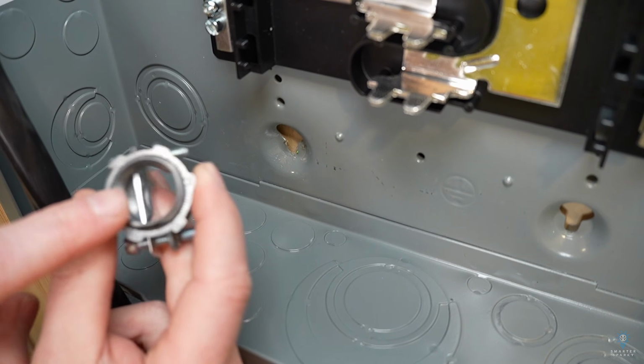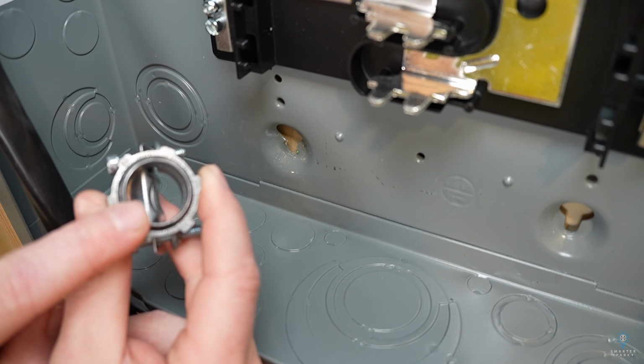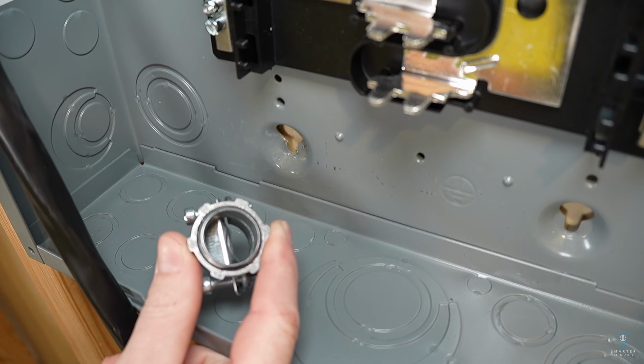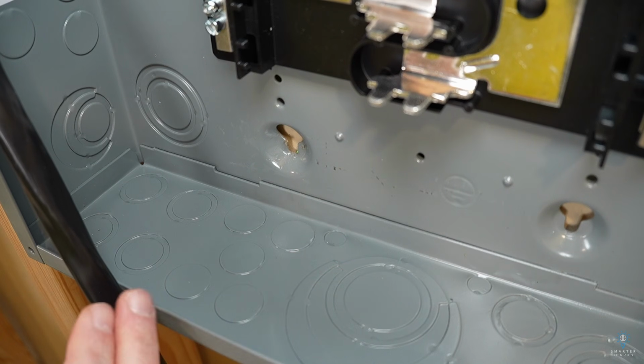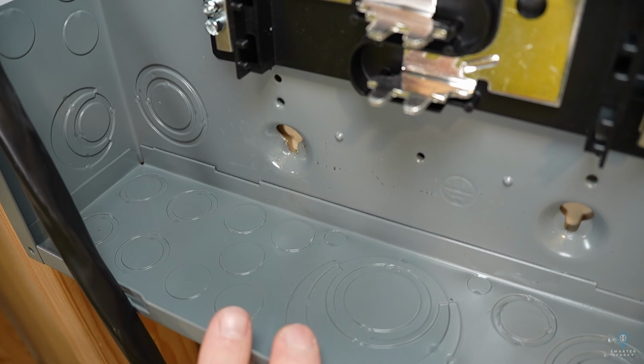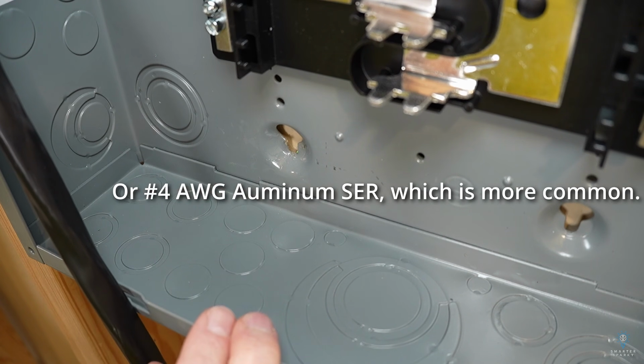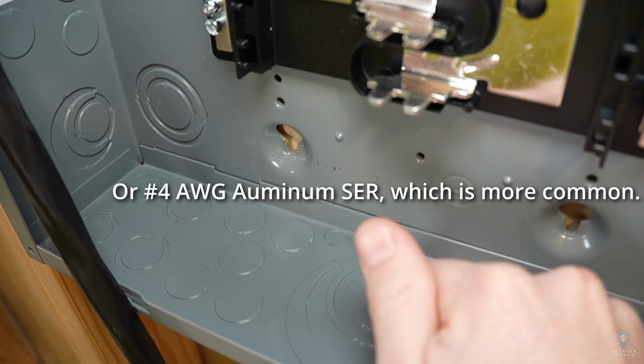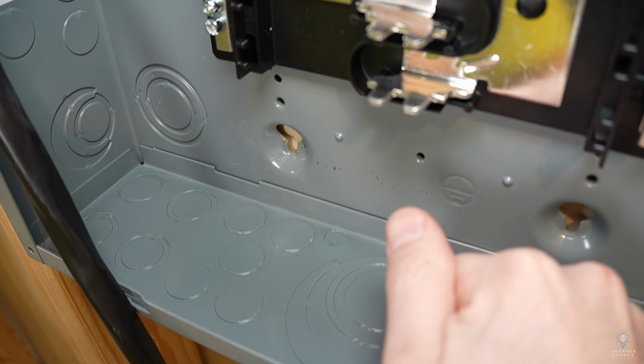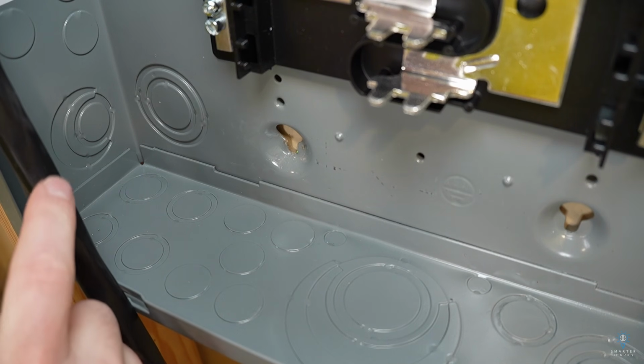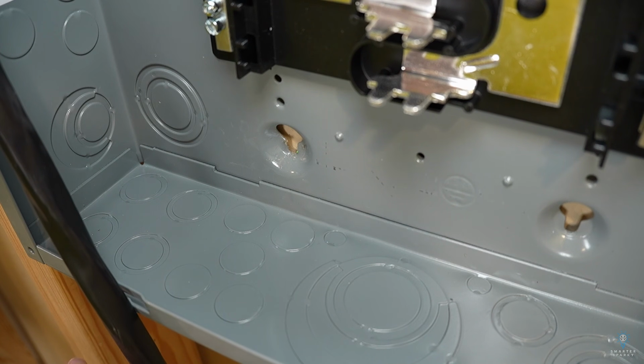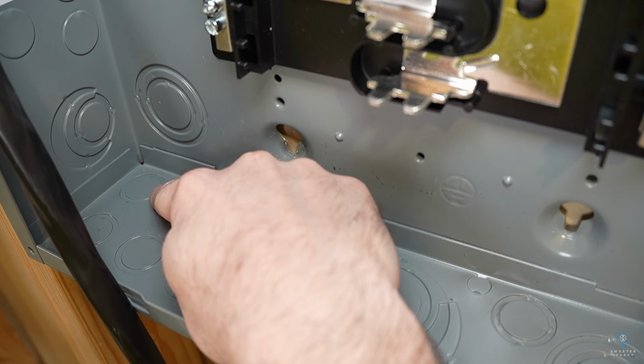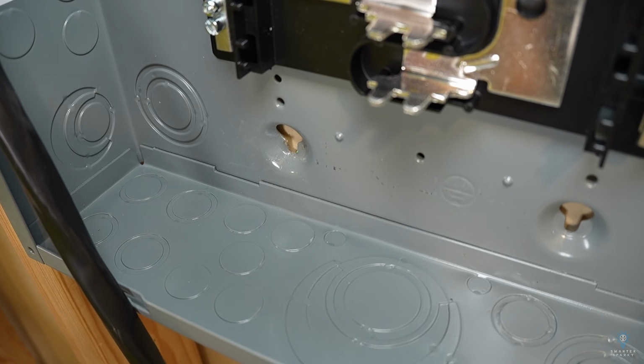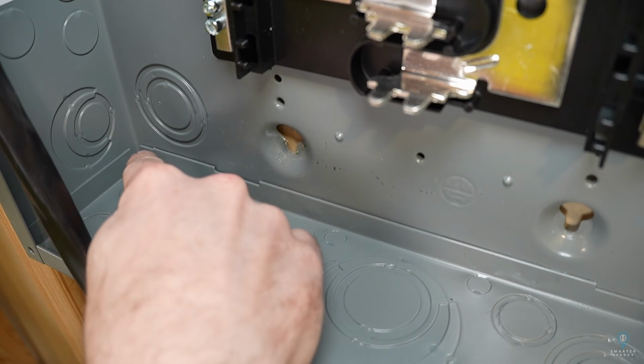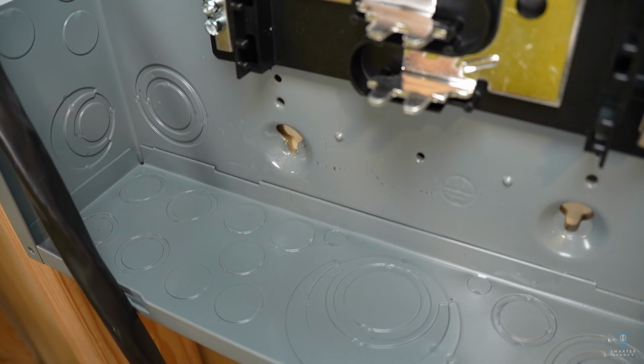This cable that we're using is small enough to actually fit in a 3/4 inch Romex connector. If you were using a larger conductor such as 3-gauge SER, if you were running a 100 amp sub panel, you might have to knock out some of these knockouts here in the middle. These are gonna be a little bit bigger. But in this case, because this will fit in a 3/4 inch knockout, I'm actually gonna knock out this far back corner right here and install the wire right there so it can come up the side of the panel and stay out of our way.